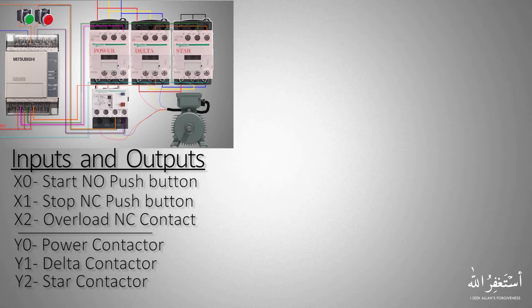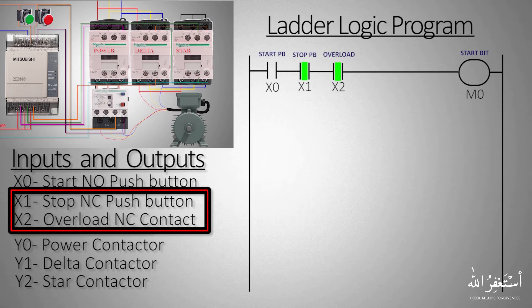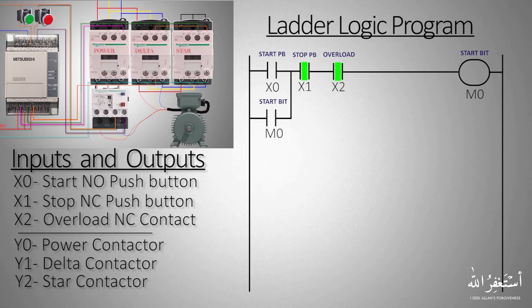Now let's start making the ladder logic. In the first rung we will put the X0 start push button, the X1 stop push button, and X2 thermal overload normally closed contact in series. If all three contacts are closed it will turn on the M0 start bit. Since X1 is a normally closed push button and the thermal overload contact is also normally closed, both contacts in the ladder logic appear closed. We then connect the normally open contact of M0 in a parallel branch with X0 to latch on the start bit M0.